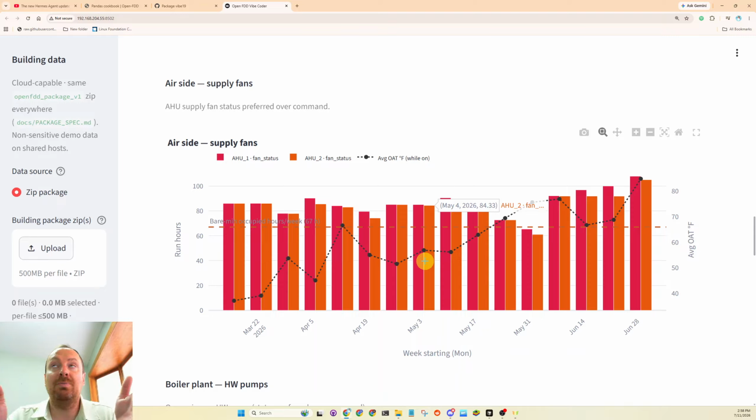And we shouldn't be economizing the air handling units all winter long, causing excess reheat energy wasted if it's a VAV system with reheats. So heating season, economizing season, and peak mechanical cooling season, three really important. And there's two shoulder seasons, obviously.